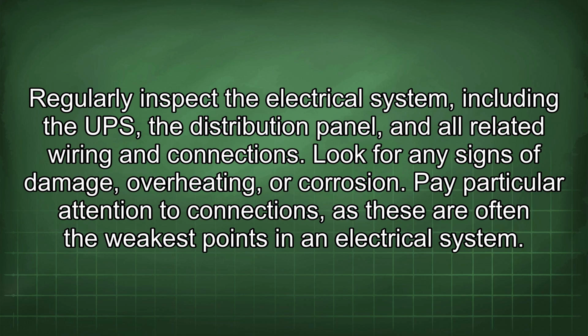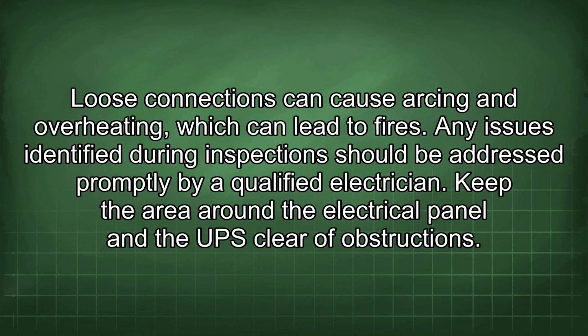Regularly inspect the electrical system, including the UPS, the distribution panel, and all related wiring and connections. Look for any signs of damage, overheating, or corrosion. Pay particular attention to connections, as these are often the weakest points in an electrical system. Loose connections can cause arcing and overheating, which can lead to fires. Any issues identified during inspection should be addressed promptly by a qualified electrician.